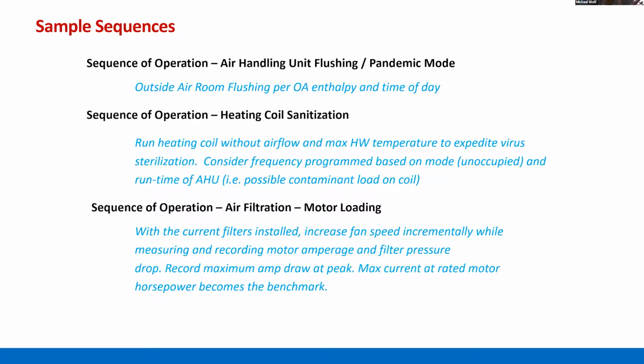We also have seen a higher ed client with a mixed-use building. So maybe most of the building is classroom, part of it's admin space. And right now with the pandemic, we're trying to find that balance between energy and safety, so looking at what is the best sequence there. In this particular example, they actually had the occupancy sensors tied into the HVAC. So we could use those occupancy sensors to drive those zone ventilation rates, making sure that once that zone is unoccupied, so maybe the class is done, it still stays in occupied mode for at least an hour afterwards as a purge mode, at probably your max cooling rate, so that we're getting that room ready for the next set of occupants. So we're seeing some of that be effective here.